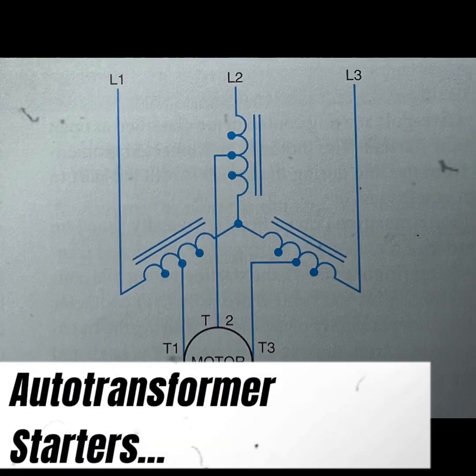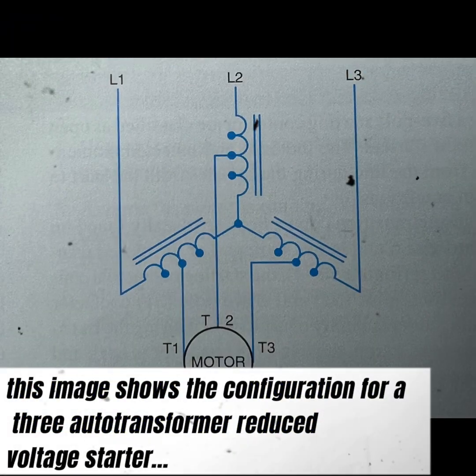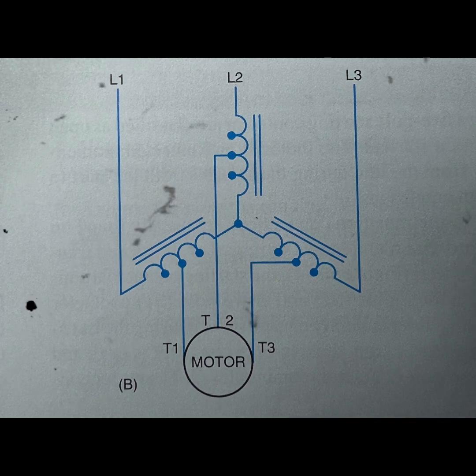Auto transformer starters. To reduce the voltage across the motor terminals during the accelerating period, an auto transformer type starter generally has two auto transformers connected in open delta. During the reduced voltage starting period, the motor is connected to the taps on the auto transformer. With the lower starting voltage, the motor draws less current and develops less torque than if it were connected to the line voltage. An adjustable time delay relay controls the transfer from the reduced voltage condition to the full voltage. A current sensitive relay may be used to control the transfer to obtain current limiting acceleration.